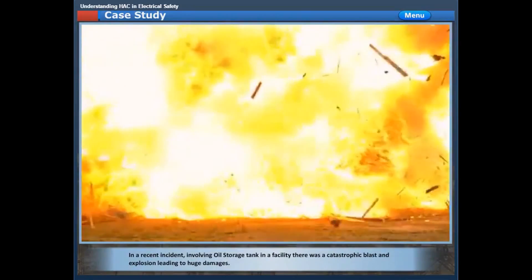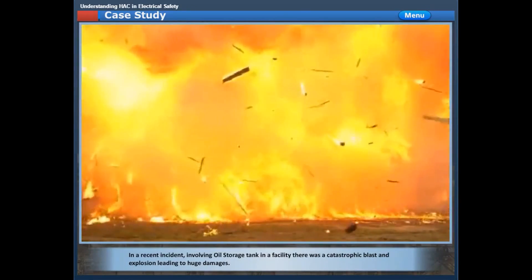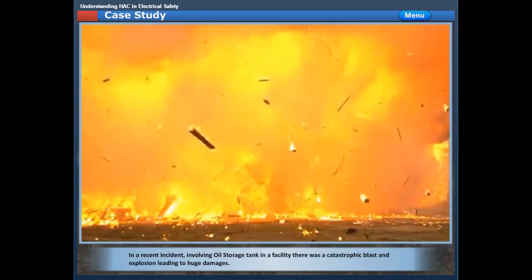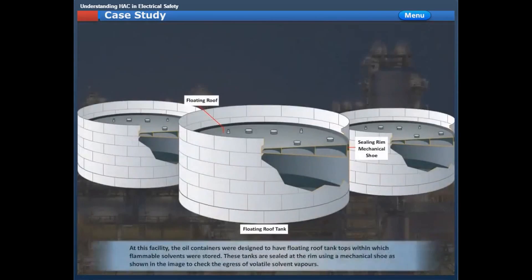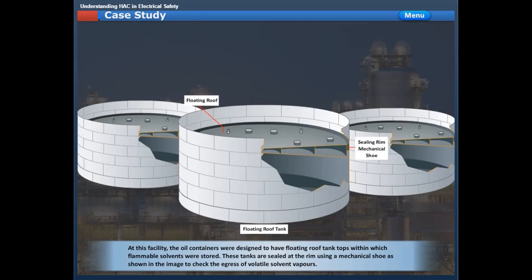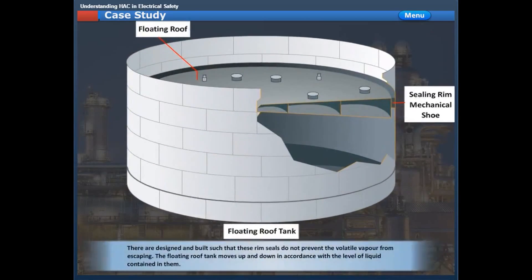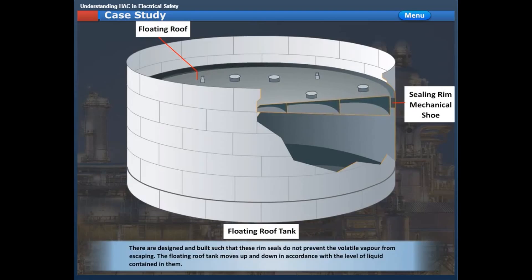In a recent incident involving an oil storage tank in a facility, there was a catastrophic blast and explosion leading to huge damages. At this facility, the oil containers were designed to have floating roof tank tops within which flammable solvents were stored. These tanks are sealed at the rim using a mechanical shoe, as shown in the image, to check the egress of volatile solvent vapors. They are designed and built such that these rim seals do not prevent the volatile vapor from escaping, and the floating roof tank moves up and down in accordance with the level of liquid contained in them.